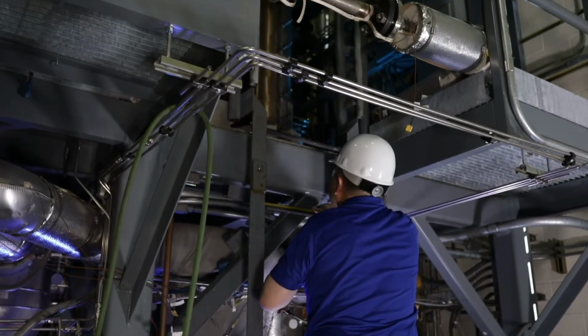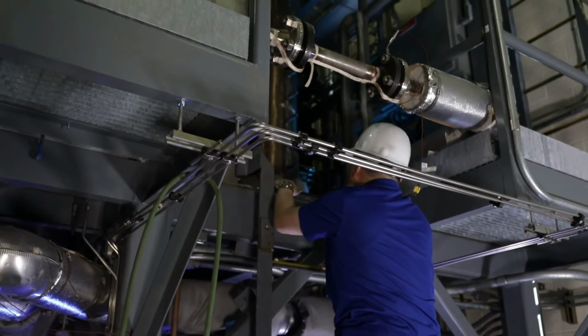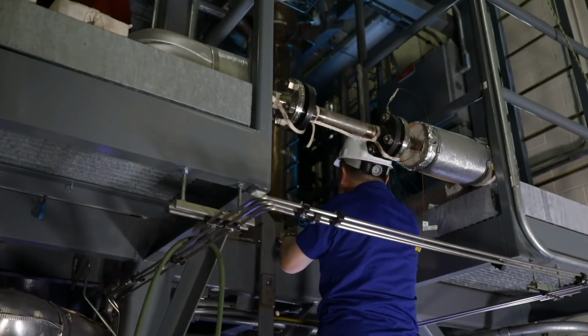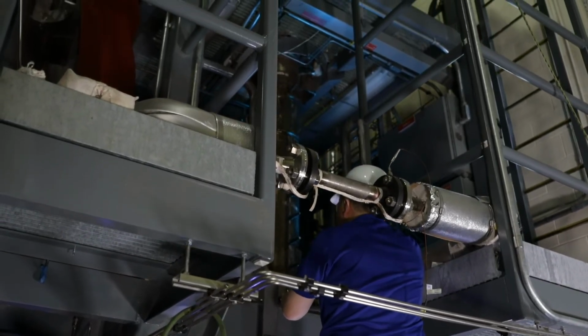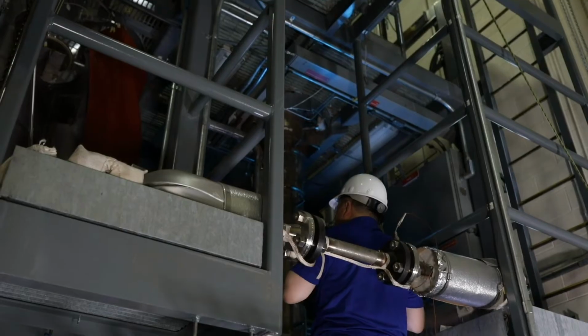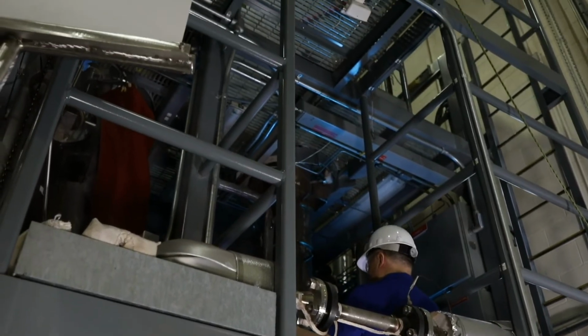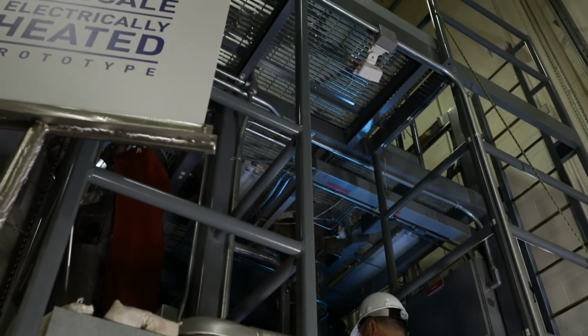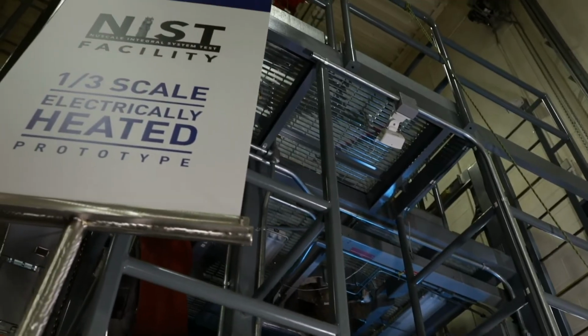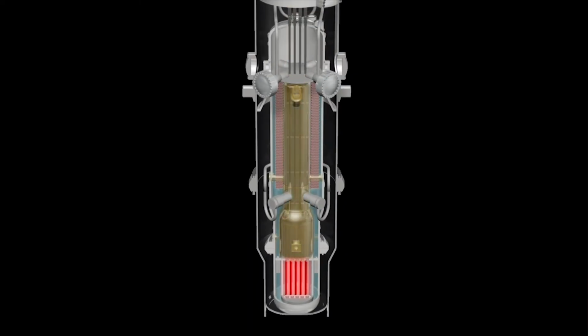The facility has demonstrated the strong safety case and viability of the NuScale power module and provides an enhanced representation of NuScale's small modular reactor design, which operates using the principles of buoyancy-driven natural circulation. This means that no pumps are needed to circulate water through the reactor. Water is heated as it passes over the core, and as it heats up, the water rises through the central riser within the interior of the vessel.